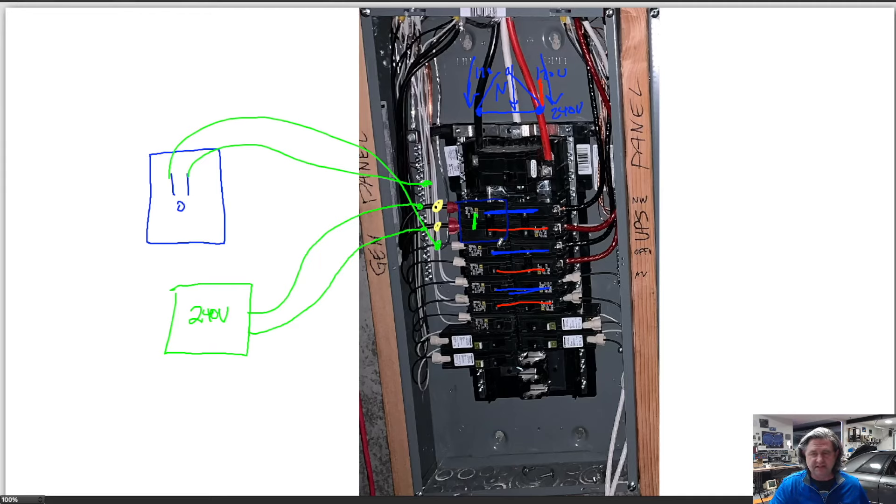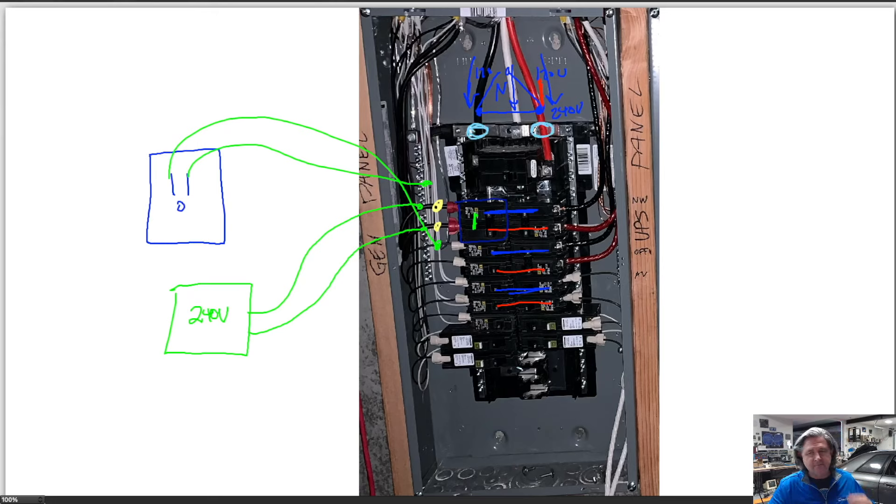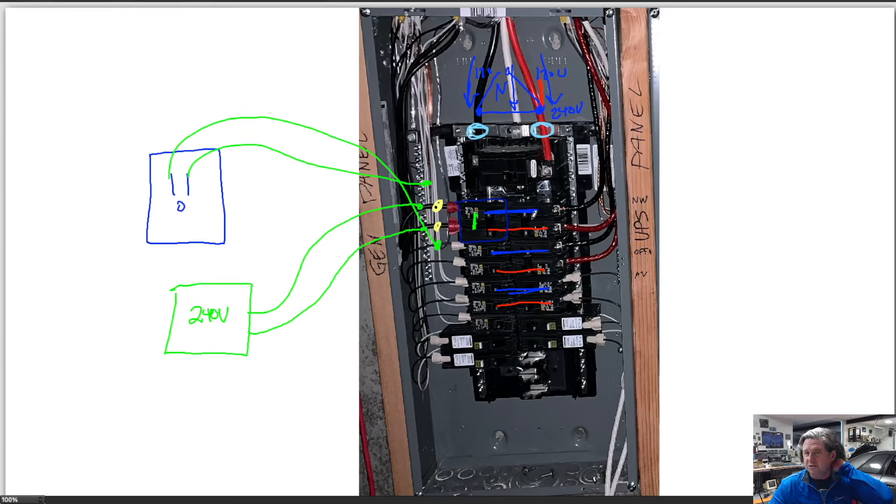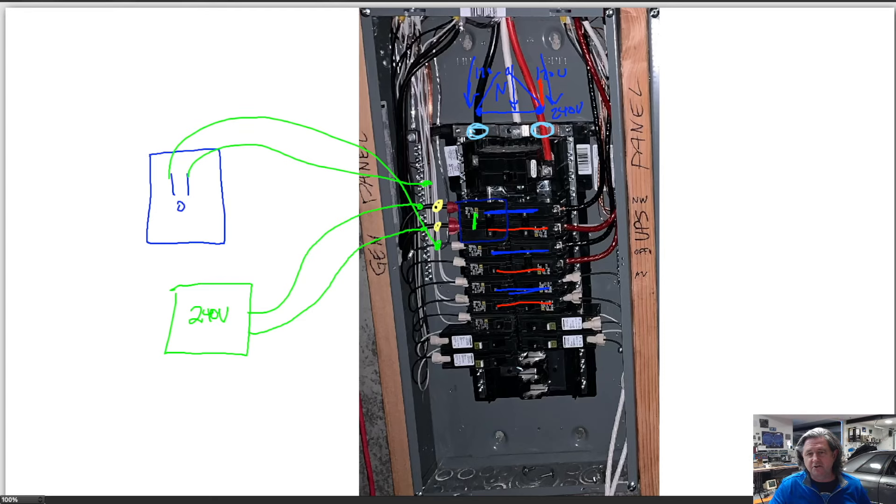What this means relative to the whole power measurement thing is that when you install CTs you typically will install probably a CT on each of the two incoming wires here, and that allows you to measure the total power coming into the panel which is kind of the upper level value you want to know.